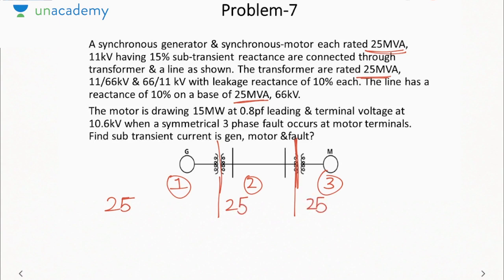Now the generator has a voltage of 11 kV, so let us say 11 kV is the base. This transformer is 11 by 66, so the secondary voltage will become 66. This is 66 by 11, so the secondary will become 11 kV. So now we have got the base of each and every section. Now the generator base remains the same, 25 MVA, 11 kV, so the reactance will also remain the same, j0.15.